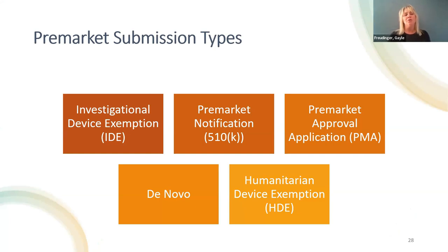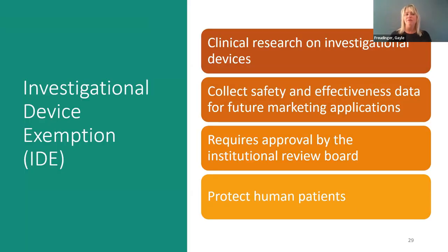So there are several pre-market submission types. This includes the IDE, which is the investigational device exemption. There is the pre-market notification, or the 510K. There's the pre-market approval application, which we call the PMA, mostly for class three devices. There's also the de novo submission, which is interesting, and we'll get to that in a moment. And then the humanitarian device exemption, or HDE. So let's quickly talk about the investigational device exemption, or the IDE.